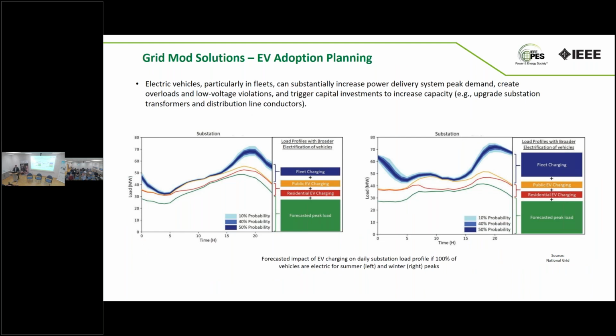Then EV adoption - we can talk about this for hours. EV adoption is very important. The challenge is that if utilities don't control or provide incentives for charging at specific hours, peak demands at the service transformer, feeder, or substation level can increase significantly. It may not be across the entire service territory, but in specific locations or clusters it may happen. That requires making investments, but the issue is you may increase capacity that's only used for a few hours every day or every year.